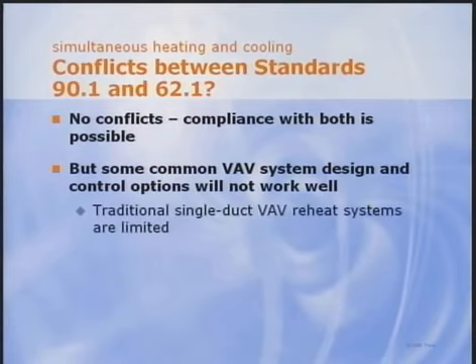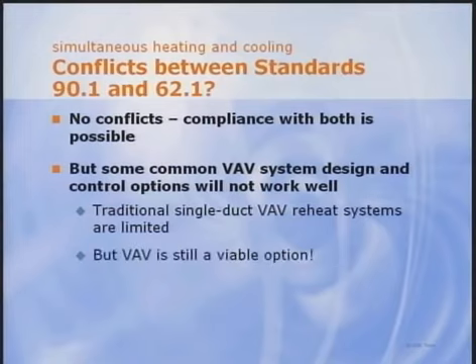In particular, for most buildings except in mild climates, traditional single duct VAV reheat systems will not work without a very high minimum outdoor air rate. It should be noted that 90.1 does not place a limit on minimum outdoor air rates, so technically almost any VAV system can be made to work. Simply supply 100% outdoor air. But that will have a first cost and energy cost impact that most designers and owners will not accept. But VAV is still an option. We will see some variations on VAV system design that can meet both standards in an efficient manner.